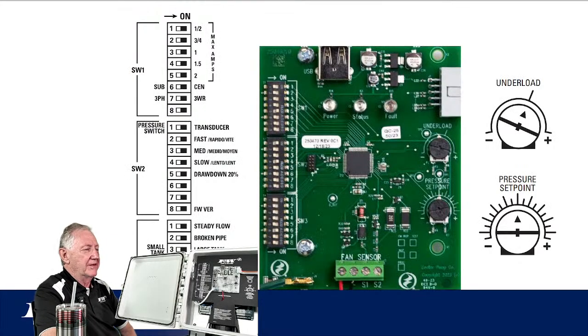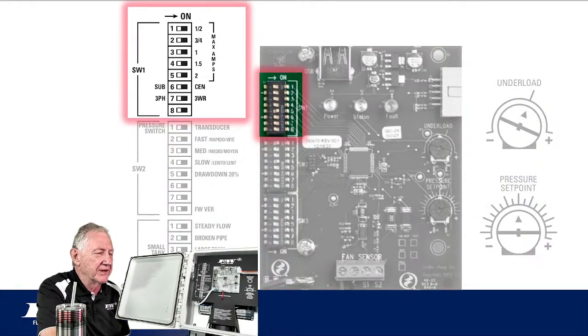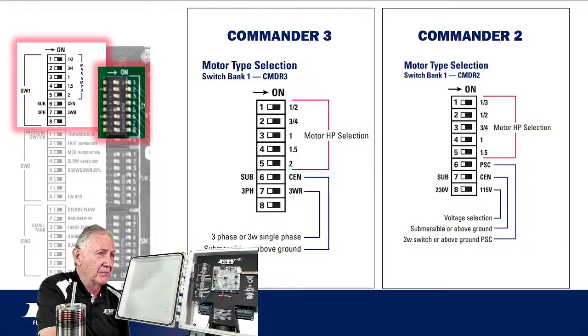Yeah, okay, we're going to move on ahead. Okay, let's look at this first bank here. Now, in that first bank, I had mentioned that up there is going to indicate what type of pump and what horsepower of pump this drive is going to operate. We've got to let the drive know what kind of pump it's going to operate.